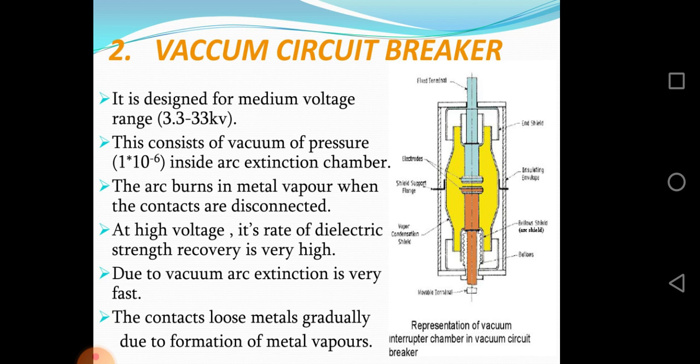Inside the arc extinction chamber, the arc burns in metal vapor when the contacts are disconnected at high voltage. Its rate of dielectric strength recovery is very high due to vacuum, so arc extinction is very fast. The contacts lose metal gradually due to formation of metal vapors. This diagram represents a vacuum interrupter chamber in a vacuum circuit breaker.